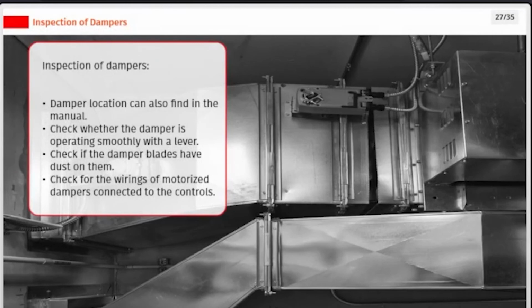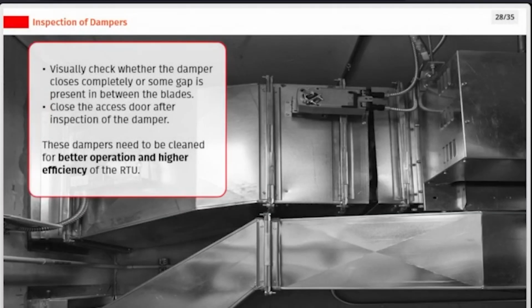Inspection of dampers. The damper location can also be found in the manual. Check whether the damper is operating smoothly with a lever. Check if the damper blades have dust on them. Check the wirings of motorized dampers connected to the controls. Visually check whether the damper closes completely or some gap is present in between the blades. Close the access door after inspection of the damper. These dampers need to be cleaned for better operation and higher efficiency of the RTU.